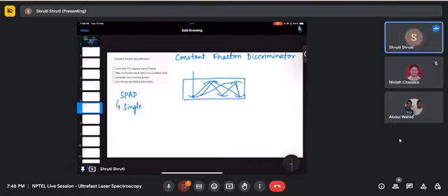It is not that only one single photon is emitted from the sample. See, the sample may emit, as per its quantum yield or efficiency, definitely millions and billions of photons. But our system is designed such that once we identify one photon, the first photon, maybe slow, delayed, whatever it may be, as per its process signature, the system is automatically stopped.